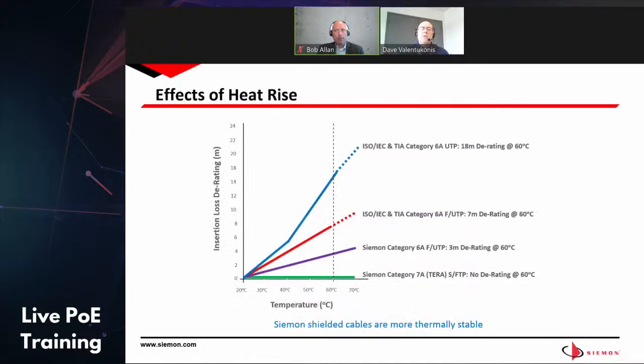So ultimately, you have to apply a certain level of derating if you're addressing temperatures up to 60 degrees. When we say up to 60 degrees, we're assuming an ambient temperature of about 45 degrees C with a heat rise of about 15 degrees C, which gets you up to the 60 degrees C typical jacket rating of these cables.